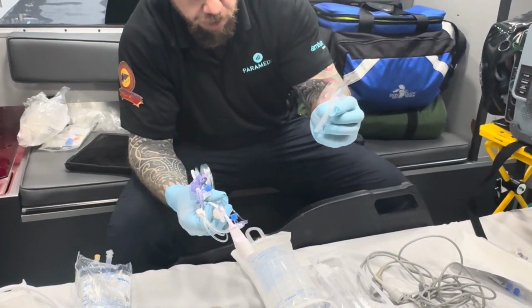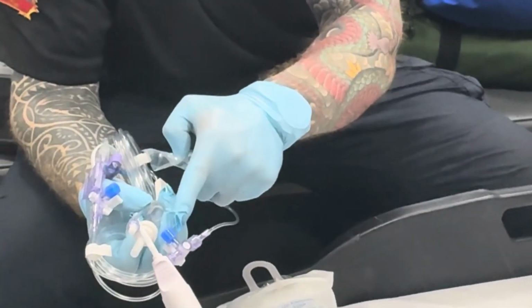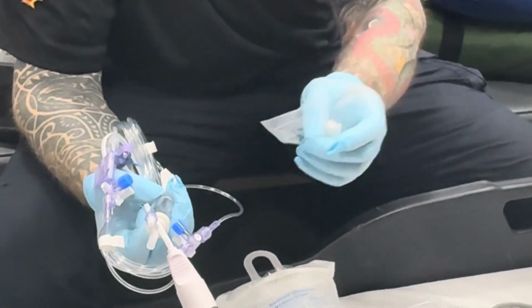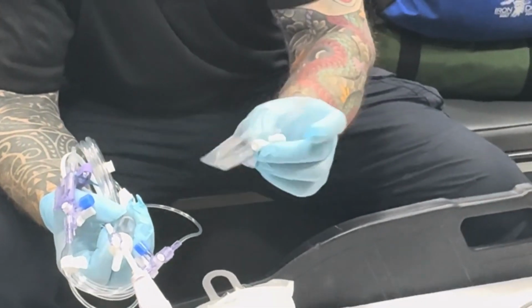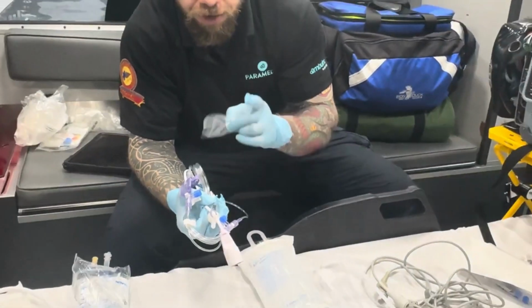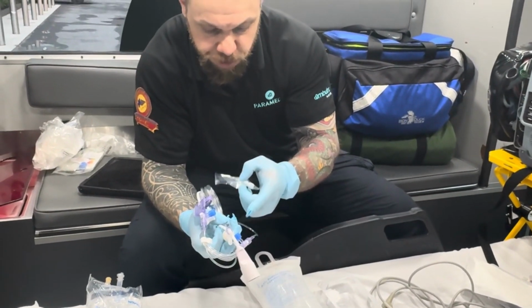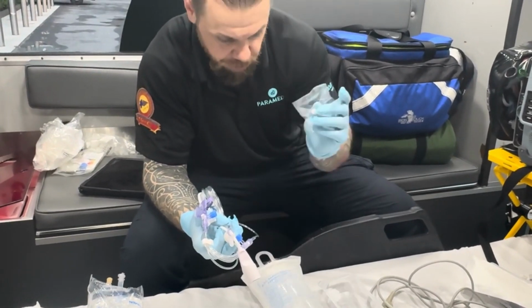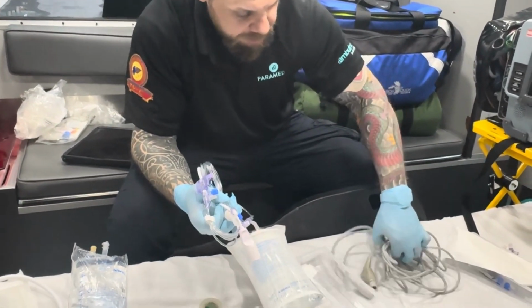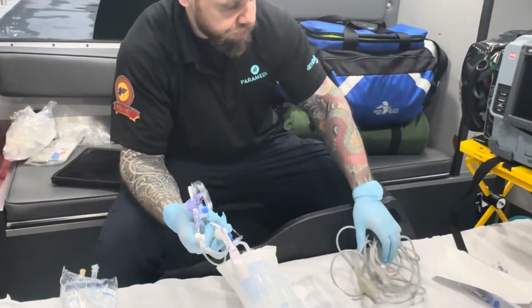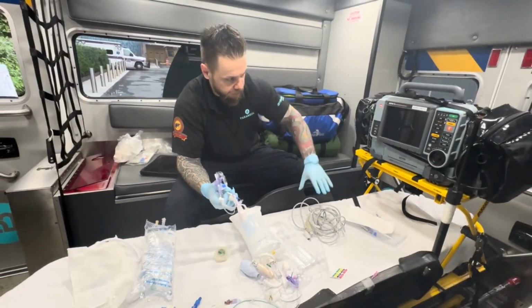These are very important caps. The caps that are currently on have holes. They're called fenestrated caps. These caps do not have holes, and you're going to replace these caps with the fenestrated ones. The reason why you need holes now is so that we can flush the system. So we got that. You're going to need the appropriate size cable that connects to your LifePak 15 right here. So I got the cable.